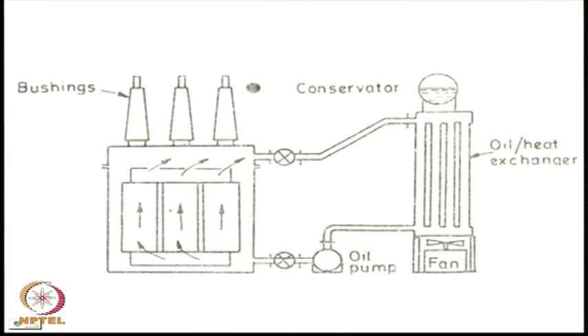So, the natural cooling by oil works this way. As the oil heats up, it becomes lighter, moves upward and comes in contact with the transformer tank wall, through which this heat is dissipated to the ambient. This is called oil natural cooling.